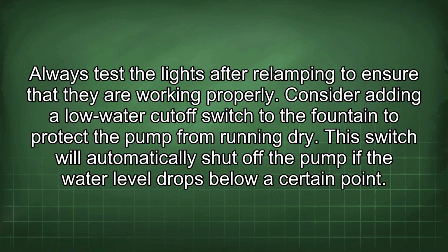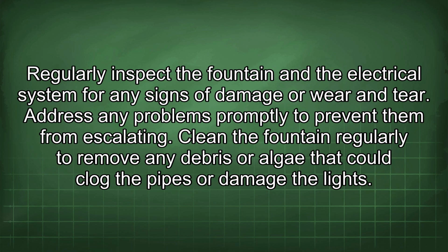Consider adding a low water cut-off switch to the fountain to protect the pump from running dry. This switch will automatically shut off the pump if the water level drops below a certain point. Regularly inspect the fountain and the electrical system for any signs of damage or wear and tear. Address any problems promptly to prevent them from escalating. Clean the fountain regularly to remove any debris or algae that could clog the pipes or damage the lights.